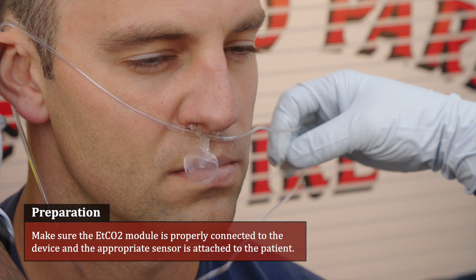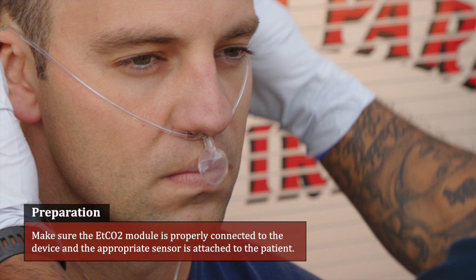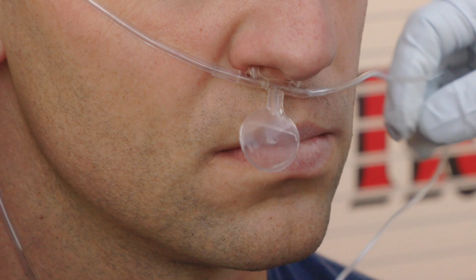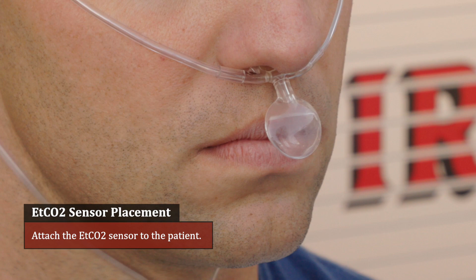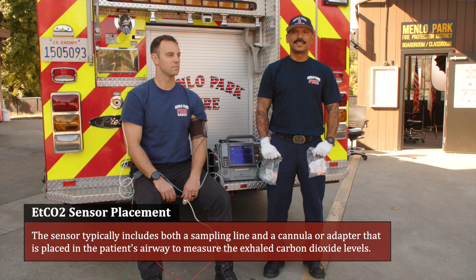Make sure the end-tidal CO2 module is properly connected to the device and the appropriate sensor is attached to the patient. Place the patient in a position of comfort for monitoring. They may be intubated or using a face mask for ventilation. Attach the EtCO2 sensor to the patient. The sensor typically includes both a sampling line and a cannula or adapter that is placed in the patient's airway via ET tube, supraglottic airway, etc. to measure the exhaled carbon dioxide levels.